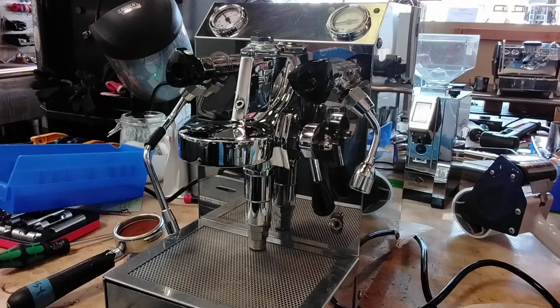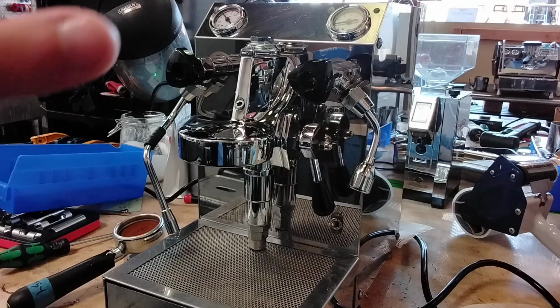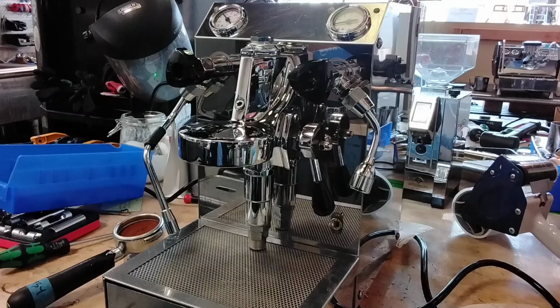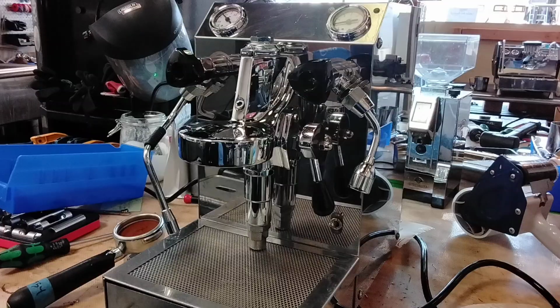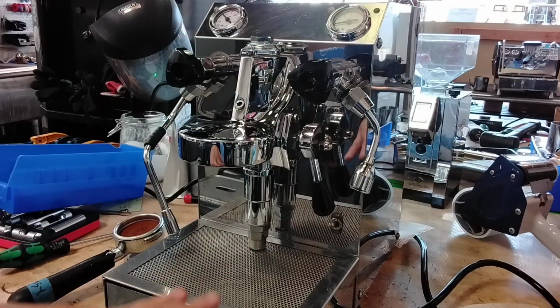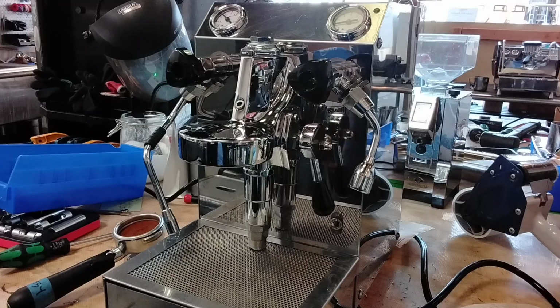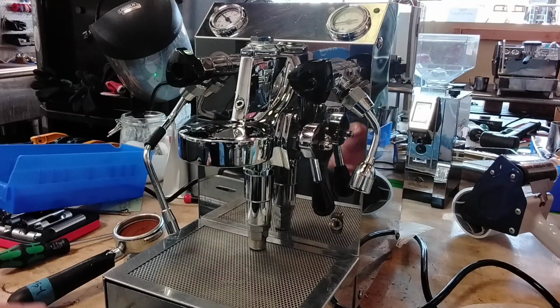What we found is that the gauges were getting a lot of condensation on the right side of the machine due to the vacuum release valve and the water level probe. The water level probe had a lot of scale around it, so the water level would rise up much higher than it should. The vacuum release valve, which is in charge of closing off the steam boiler when it's pressurized, was leaking from its gasket.